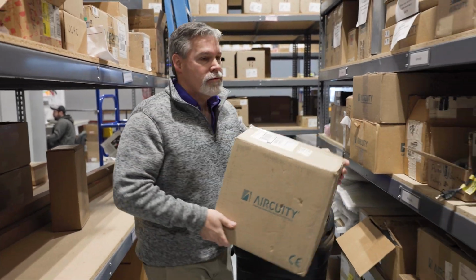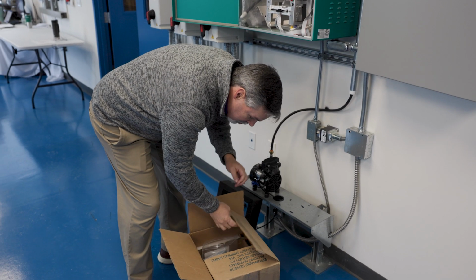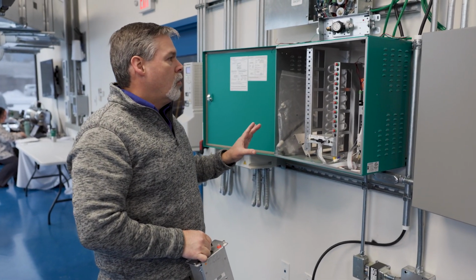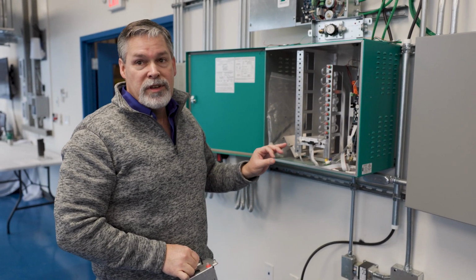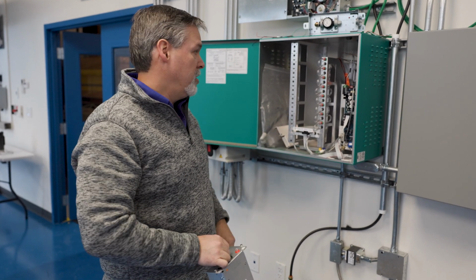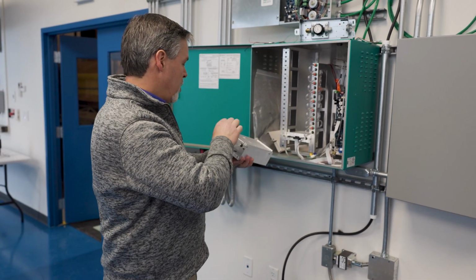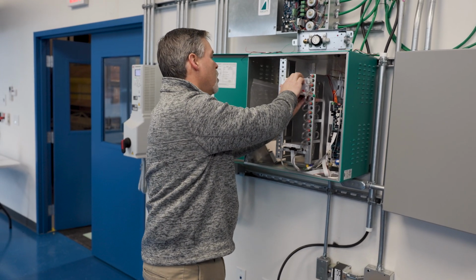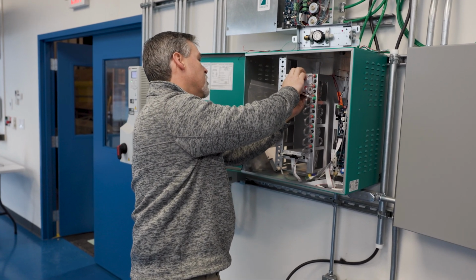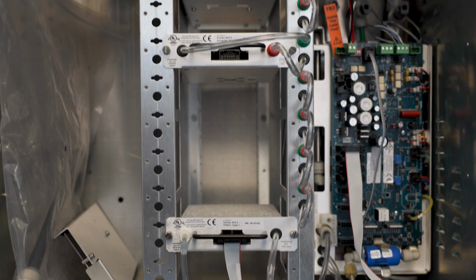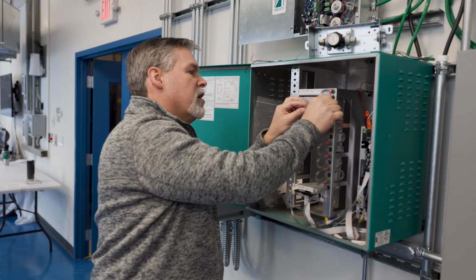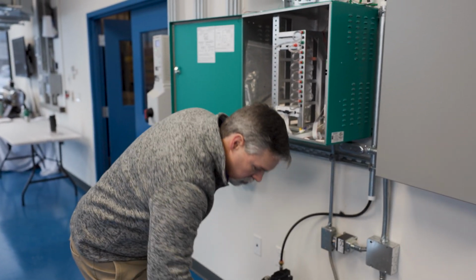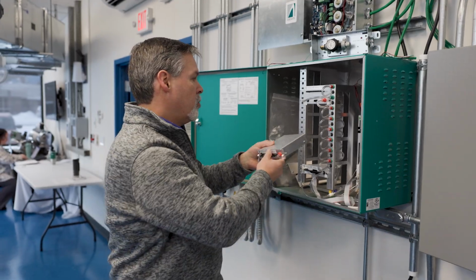What they would be doing is going to the job site, and they may have 1 sensor suite like we have here, or we have jobs that have upwards of 10 or more, in some cases. They would be pulling the old sensors out and replacing them with newly calibrated sensors that come from Aircuity's calibration lab. These get put in line and attached to the sensor rail. This is a carbon dioxide sensor, and this other one is a dew point sensor.